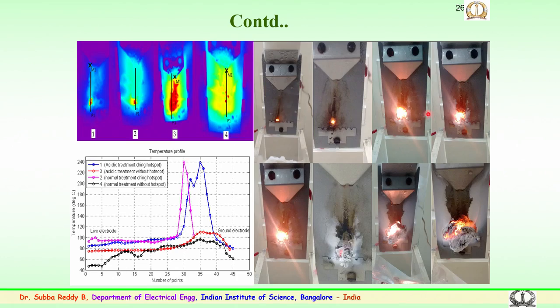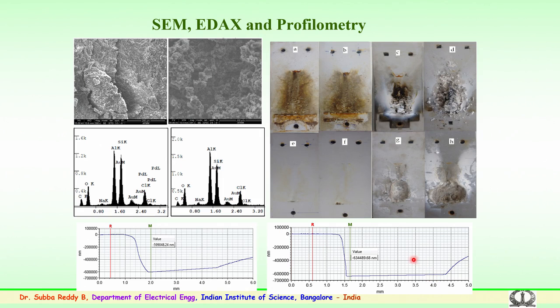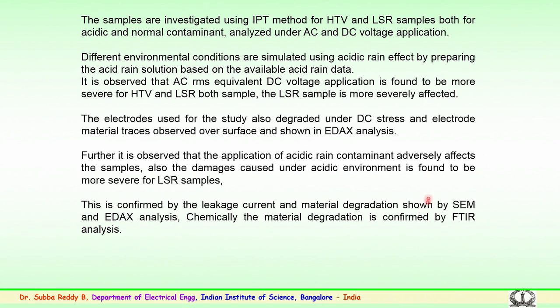The degradation from the inclined plane experimentation happens at several locations. These are the various samples showing the degradation which has occurred — surface morphological studies have been carried out on samples investigated using the inclined plane method, particularly for high temperature vulcanized (HTV) and liquid silicone rubber (LSR) samples, for both acidic and normal contaminants, analyzed under both AC and DC voltage applications.